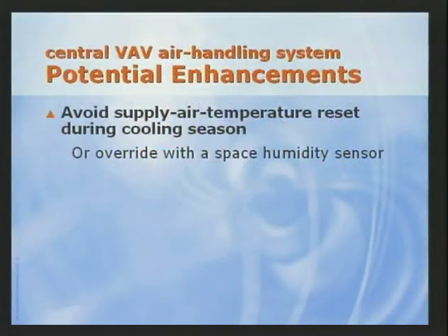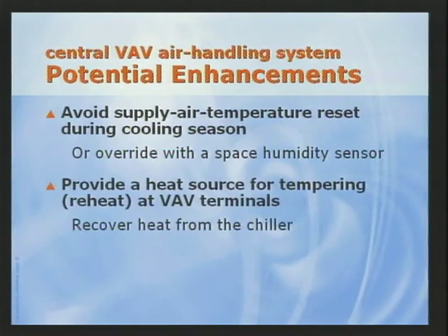First, avoid using supply temperature reset during the cooling season. But if you do use it, consider providing a humidity sensor to override it if space humidity rises too high. Second, be sure to provide a source of heat for tempering at low cooling loads. Again, if using a hot water boiler, it needs to be available to operate during the cooling season. Alternatively, consider recovering heat from another part of the system.